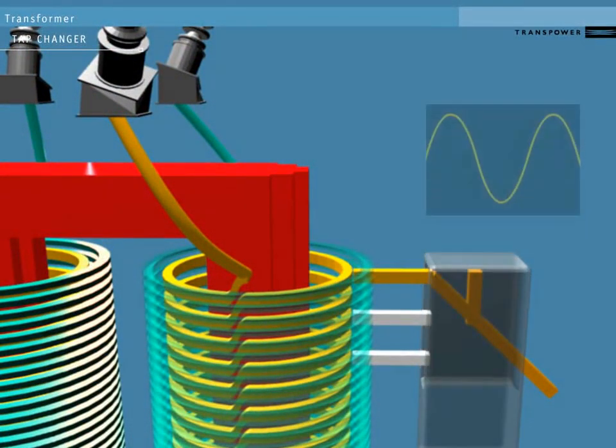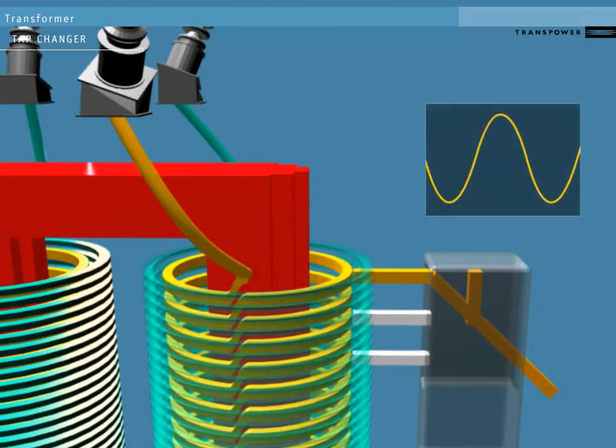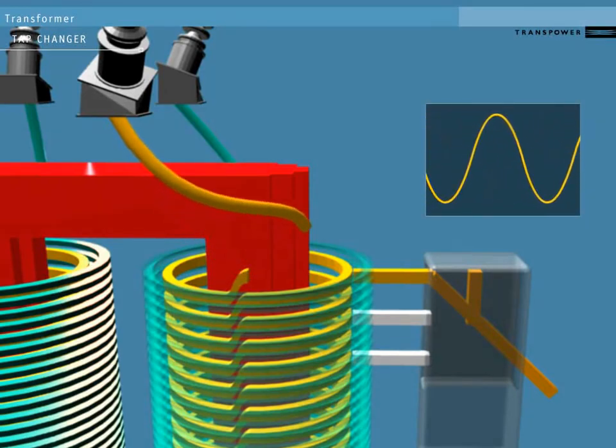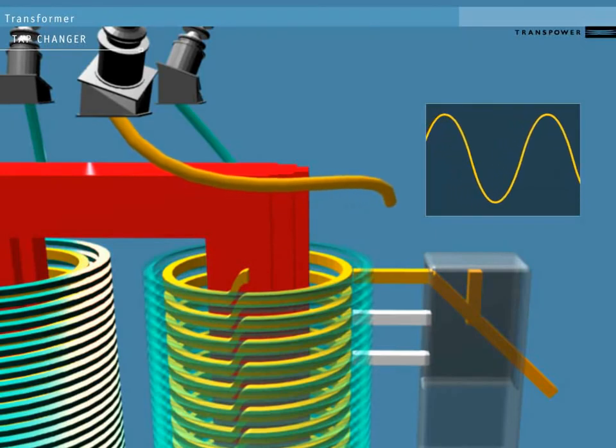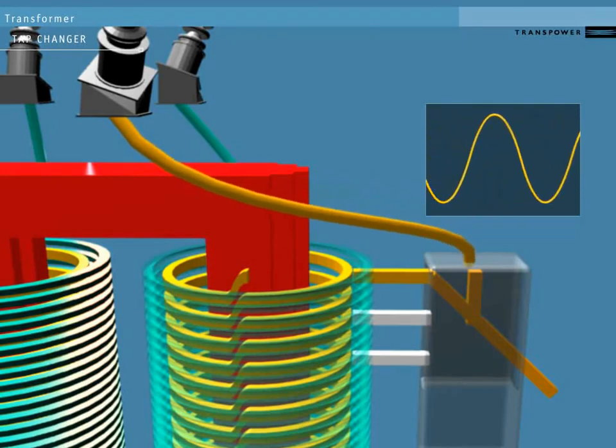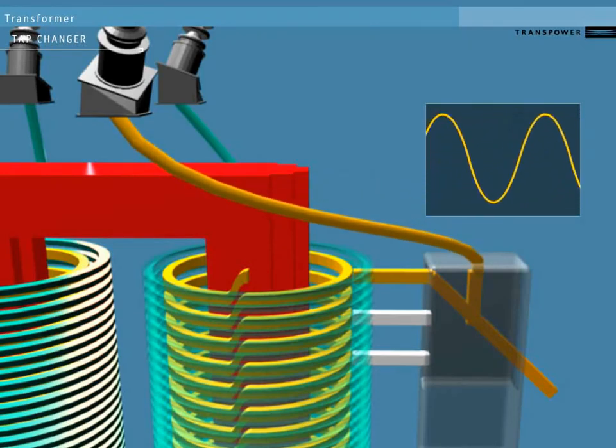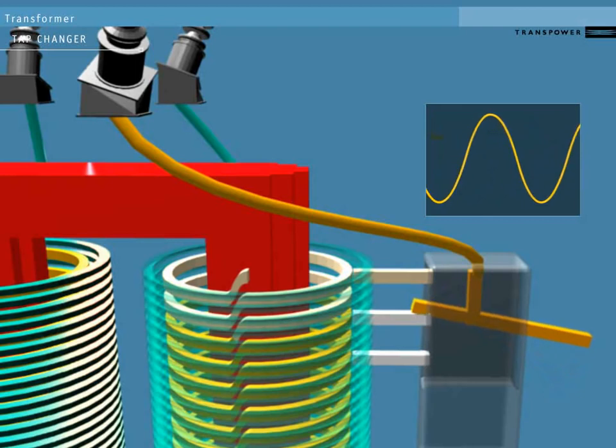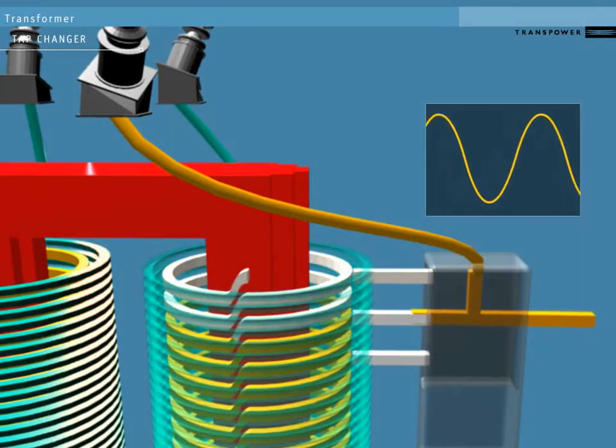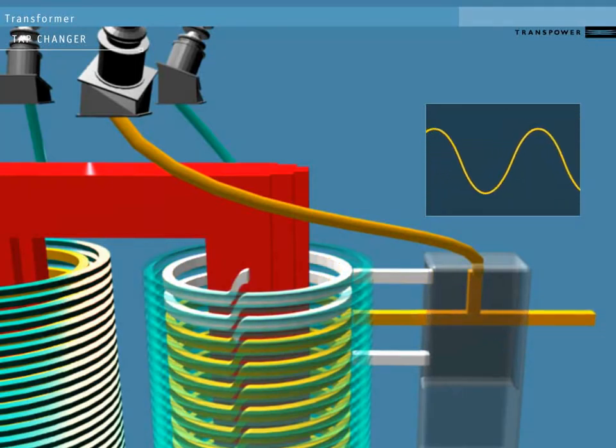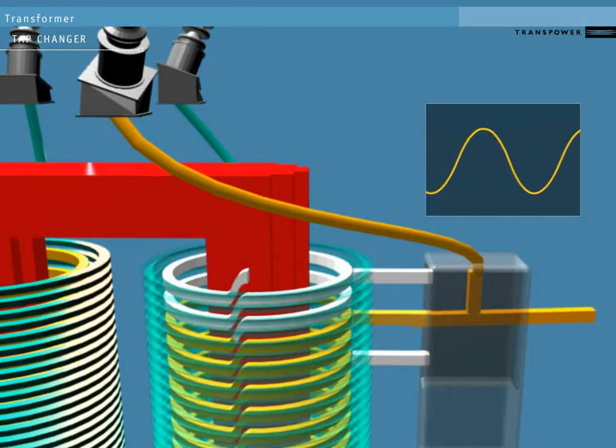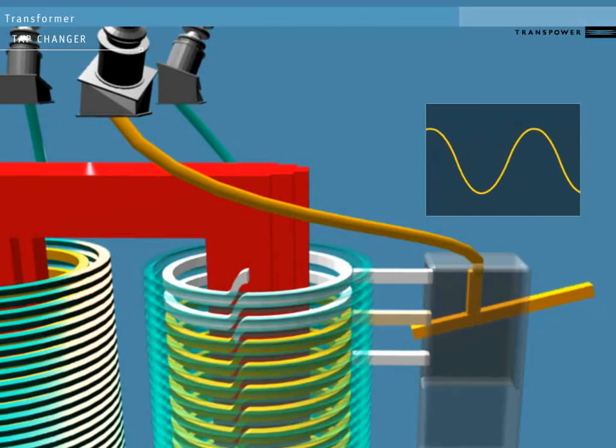To adjust the final voltage further, we can use tap changers. These reduce the number of windings on the low voltage side still further by changing the location of the conductor that leads out of the transformer. Notice how the sine wave reduces as the tap changer connects to fewer windings, reducing the voltage.